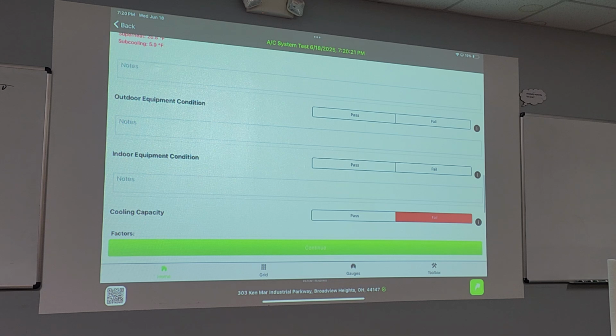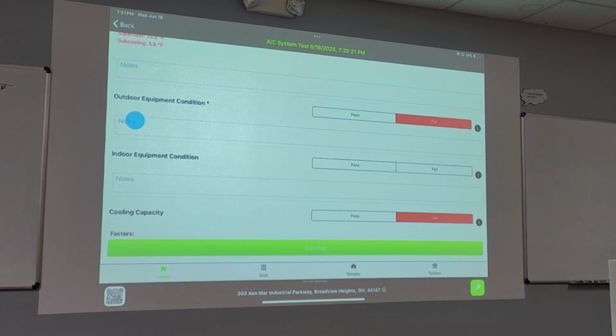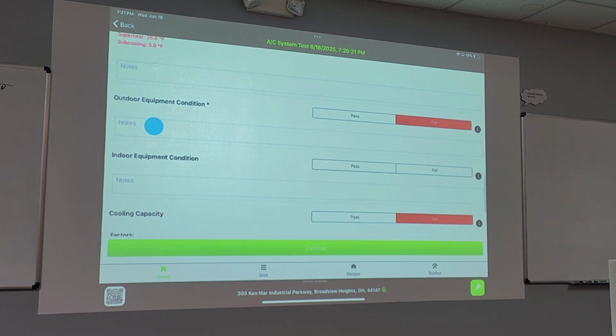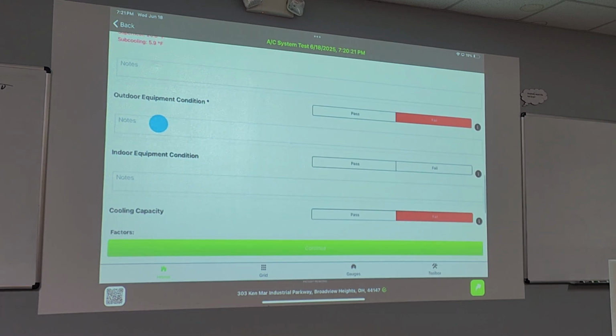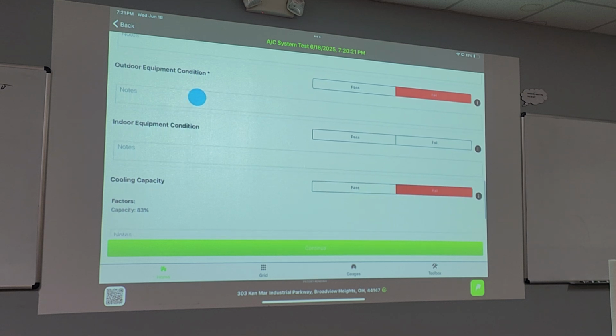Next is outdoor and indoor equipment condition—this is just cosmetic condition. We've already documented the performance thoroughly, so now you're just noting whether it's physically in good shape. This is where, if whoever's cutting the grass needs to learn how to run a weed whacker instead of tearing up the condensing unit outside, you document that here. This is customer facing and will be on the report, so note anything you observed—cover your ass here.